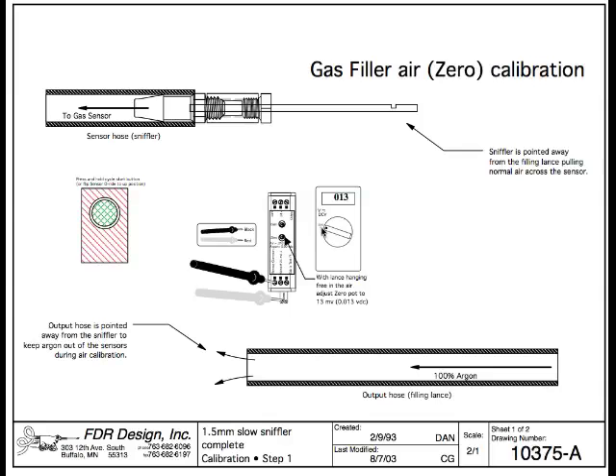Turn your voltmeter to DC volts, 2000 m. If it's not an auto ranging meter, you're going to have to set the range to 2000 m. And then again, with the sniffler sucking only air in, we're going to want to put our black lead on sensor common screw terminal, which is the bottom left screw terminal, and the red lead is going to go on the test tab way on the bottom of the board. With the meter set there, we're going to want to adjust the zero potentiometer until we read 13 millivolts. And that 13 millivolts again is going to tell the machine what air looks like. That's step one.